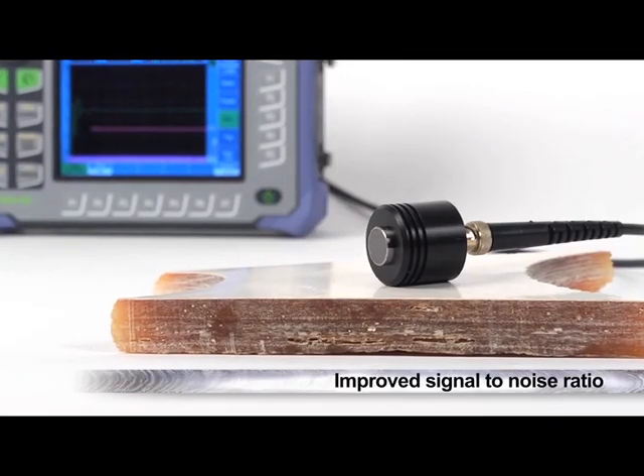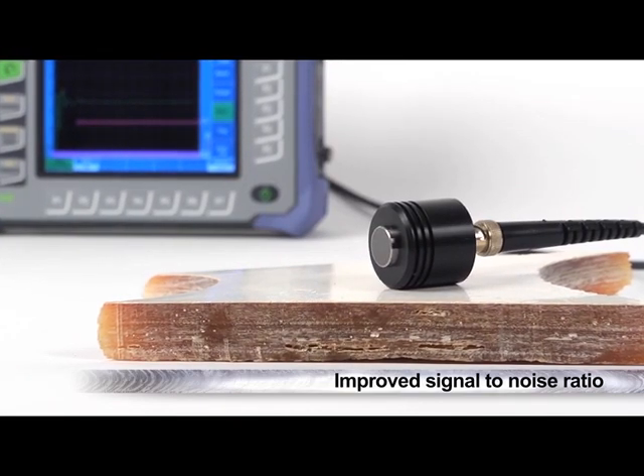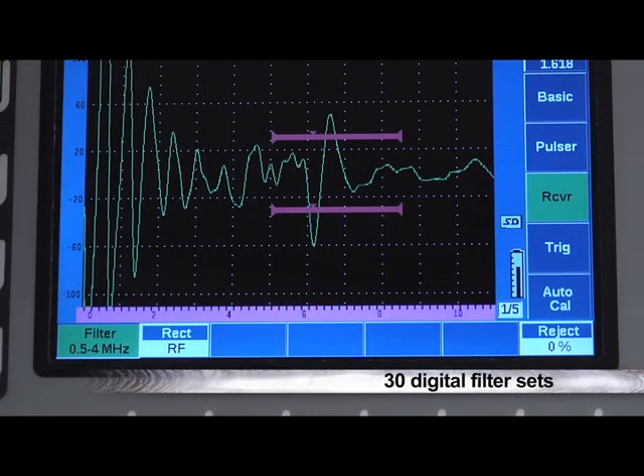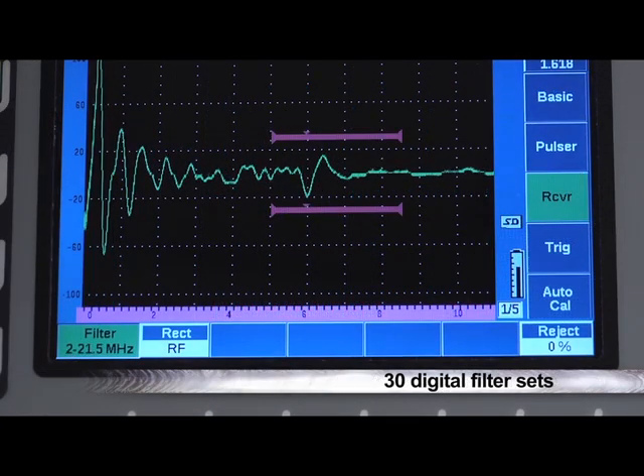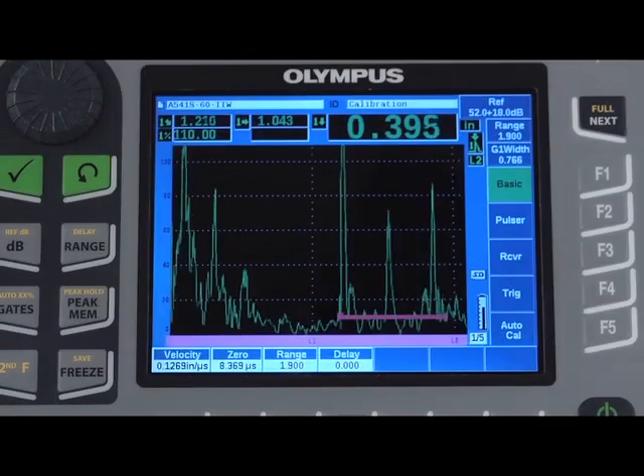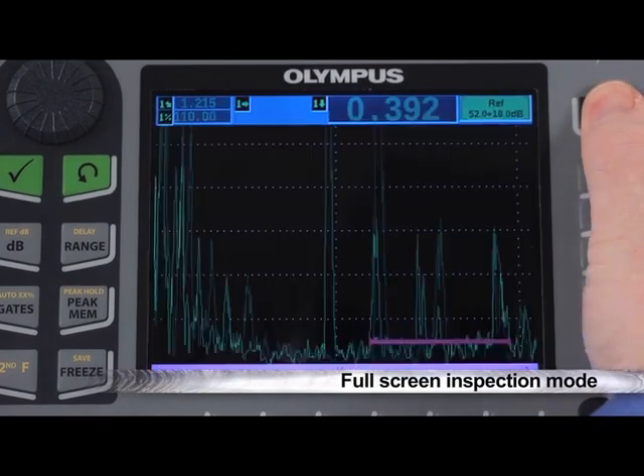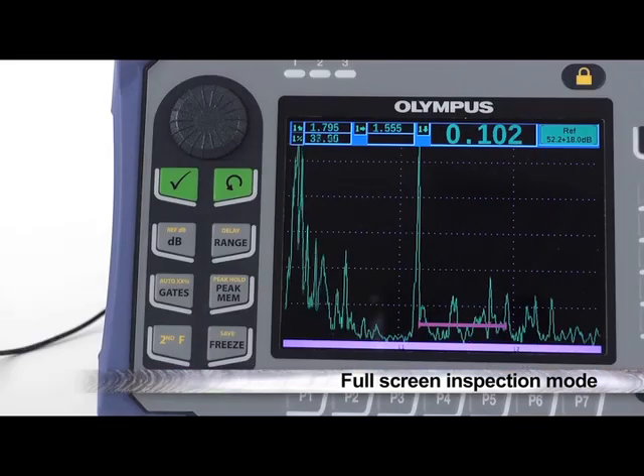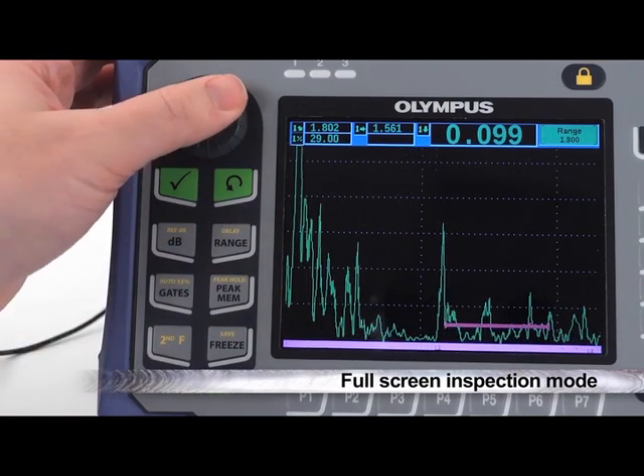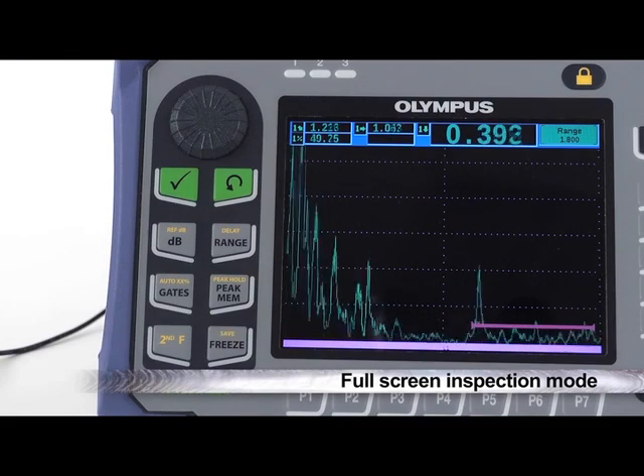Improving the signal-to-noise ratio for inspections on highly scattering or grainy materials is easily managed by the EPOCH 650's receiver filters. The instrument features 30 digital filter sets, all with industry-leading performance and optimized for near surface resolution. The EPOCH 650 allows optimal A-scan visibility during inspections through a full-screen inspection mode. While in this mode, the user still has access to all direct function keys and visibility to instrument measurements, without crowding the display with vertical and horizontal menus.